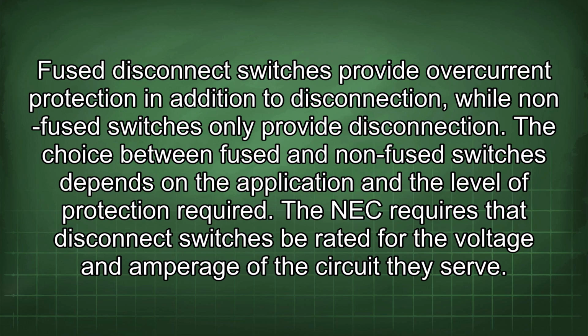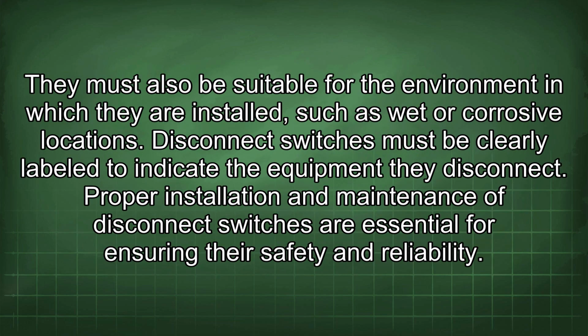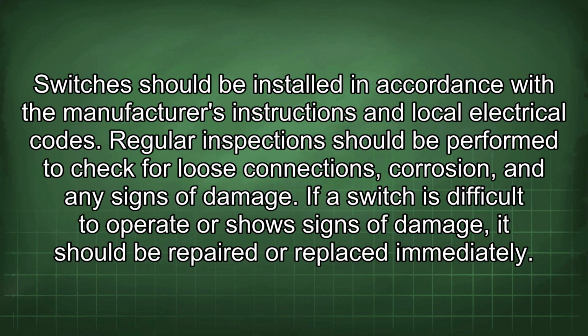The NEC requires that disconnect switches be rated for the voltage and amperage of the circuit they serve. They must also be suitable for the environment in which they are installed, such as wet or corrosive locations. Disconnect switches must be clearly labeled to indicate the equipment they disconnect. Proper installation and maintenance of disconnect switches are essential for ensuring their safety and reliability. Switches should be installed in accordance with the manufacturer's instructions and local electrical codes. Regular inspections should be performed to check for loose connections, corrosion, and any signs of damage. If a switch is difficult to operate or shows signs of damage, it should be repaired or replaced immediately.